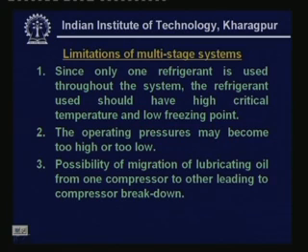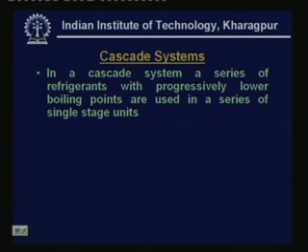Another type of system is the cascade refrigeration system. In a cascade system, a series of refrigerants with progressively lower boiling points are used in a series of single-stage units. These different single-stage systems use different refrigerants which are never physically mixed — the only connection between different stages is through thermal contact. The low-temperature system transfers heat to the high-temperature system and so on.